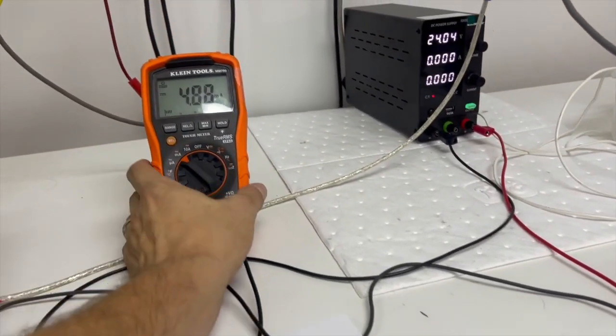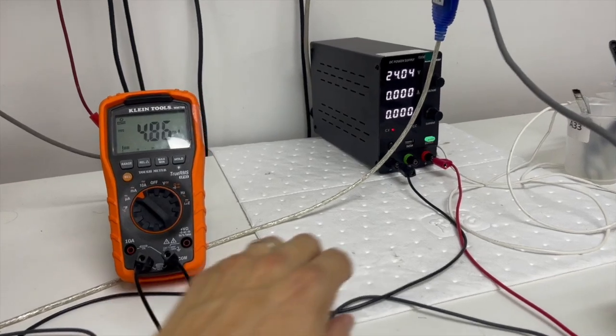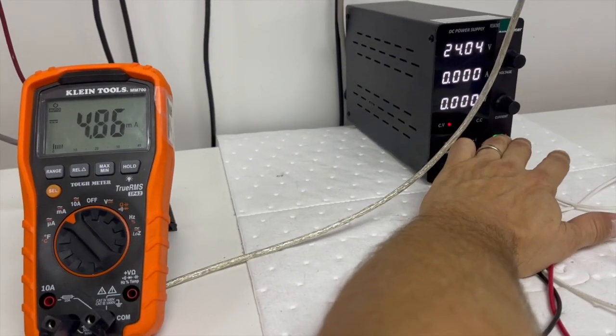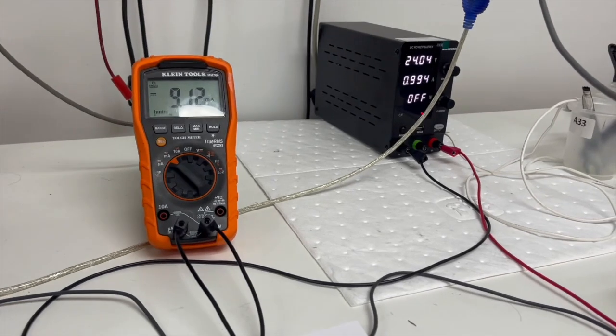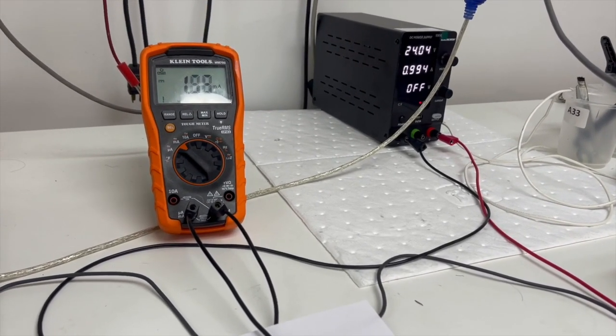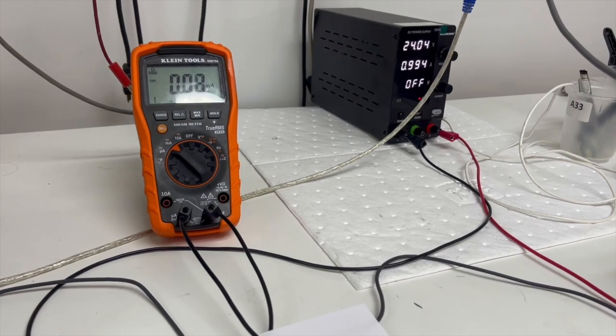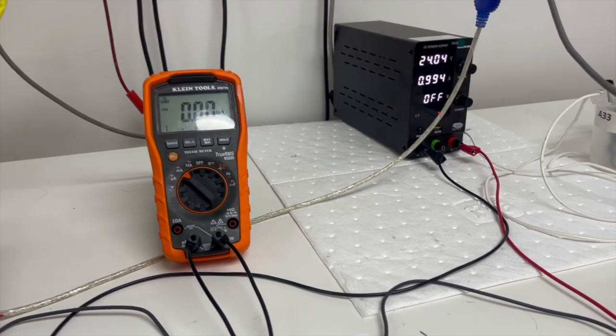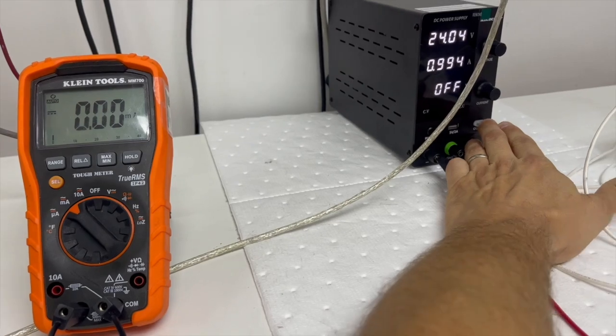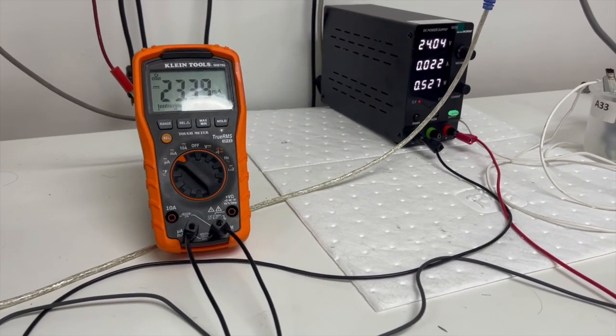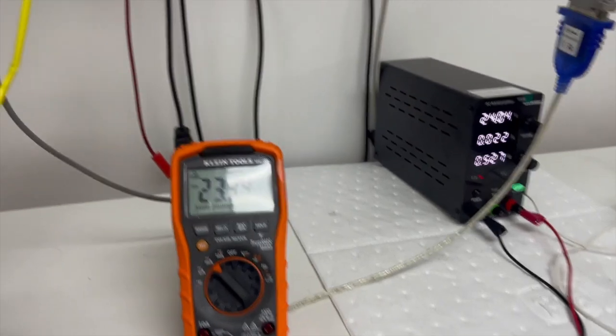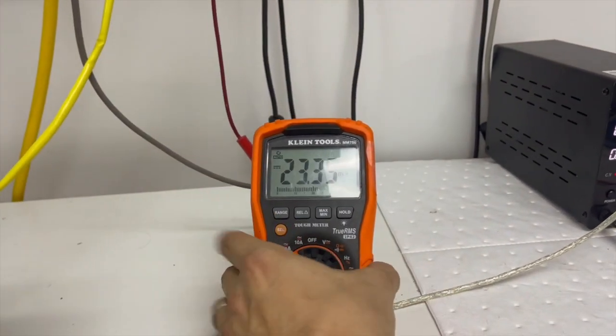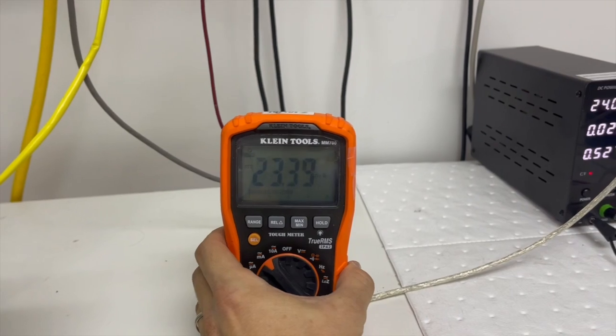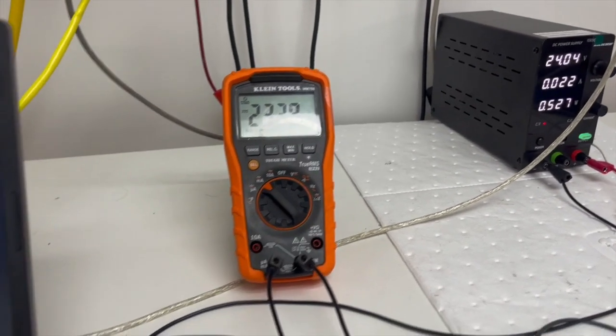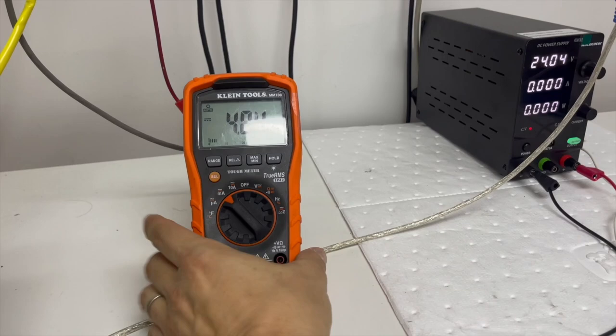So that being said, the first thing we want to do is make sure that when we first turn it on, it fires up at full scale. So we have to cut the power. Wait for it to go all the way down. And then we're going to power it up. It reads 23.39. I don't know if you can see that. 23.39 mA, which is fine. And now we want to see that it drops down to somewhere around there, 4.84.